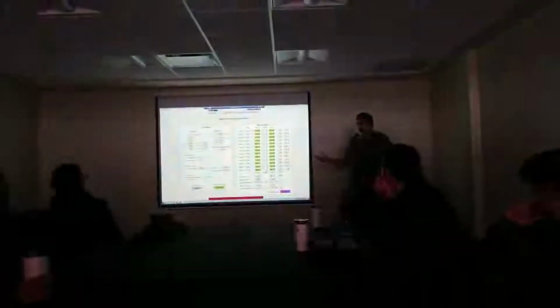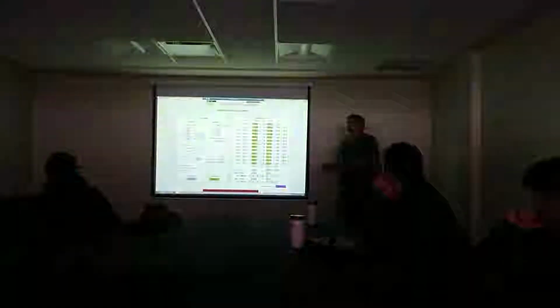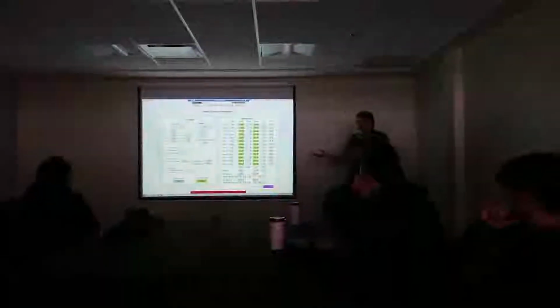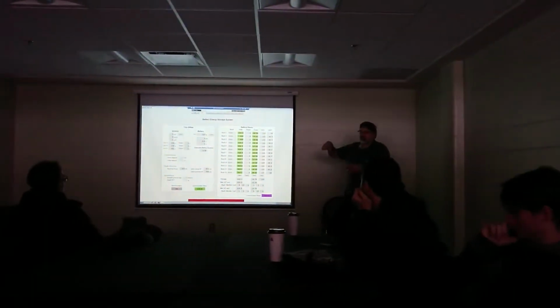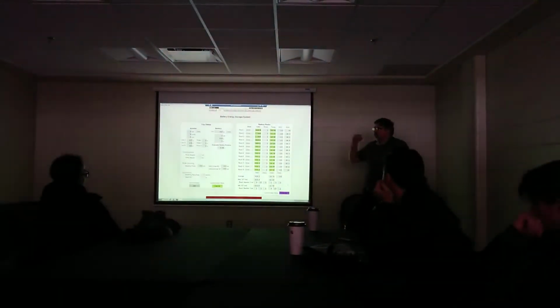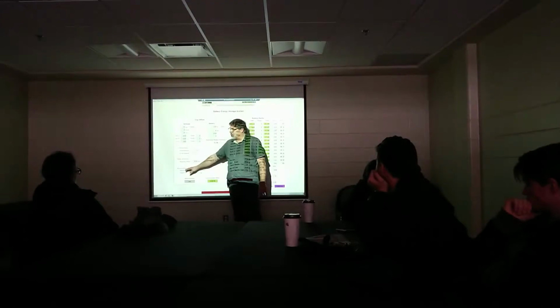With clouds coming by that way, there's not much we can do about that happening. But what we were worried about is when those clouds were going by and the power was changing that much, we could get harmonics from this system onto the grid. We haven't studied it 100% to confirm it isn't a problem, but we did look at the main meters, and we don't see any issue. During those times we checked to see how bad the harmonics are, and they don't change much from any other time. So we decided we don't really need smoothing — if we are in smoothing mode, this doesn't save us any money, but the other mode does, so that's why we want to try and keep it.